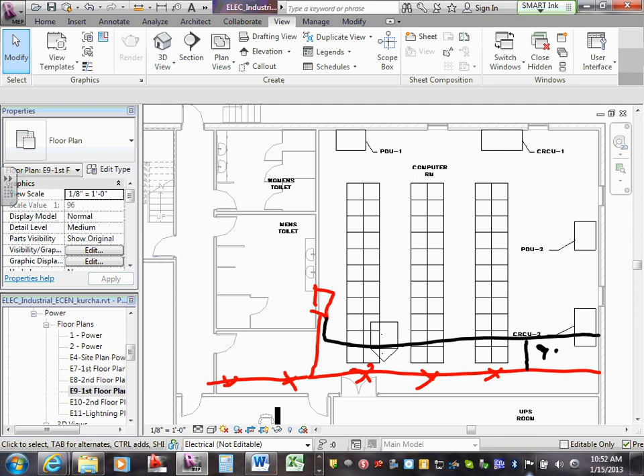These two pipes are going to be cross-zoned, so that if one zone goes off, it's not going to do anything with the pre-action system. It takes both the systems to go before any of the pre-action system will go. Typically in this area, you're going to have an emergency power-off system, so that when the pre-action system does go into alarm, EPO goes on, shuts everything down, then the water will flood into the system. You don't want to get any of this wet while it's energized.